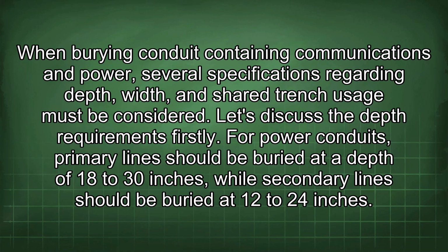When burying conduit containing communications and power, several specifications regarding depth, width, and shared trench usage must be considered. Let's discuss the depth requirements firstly. For power conduits, primary lines should be buried at a depth of 18 to 30 inches, while secondary lines should be buried at 12 to 24 inches.